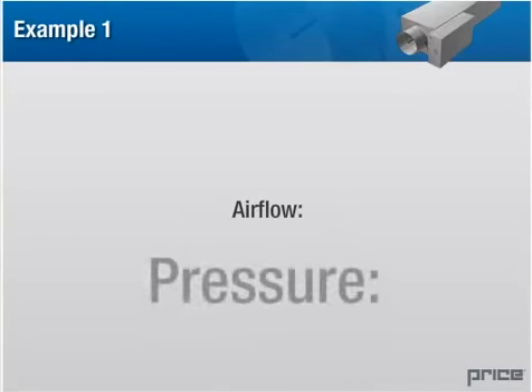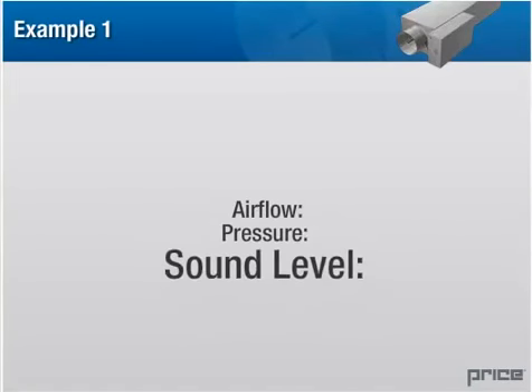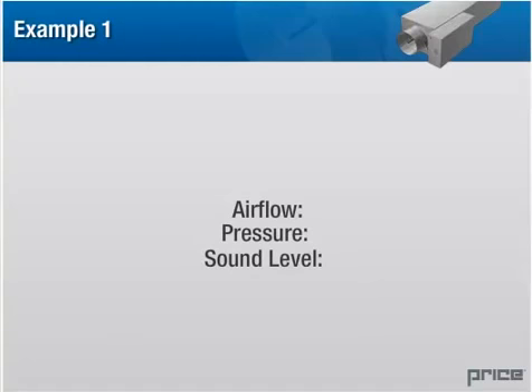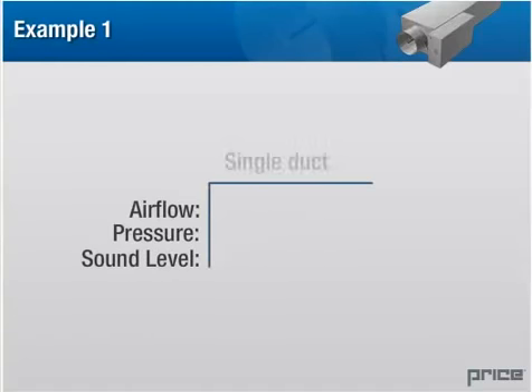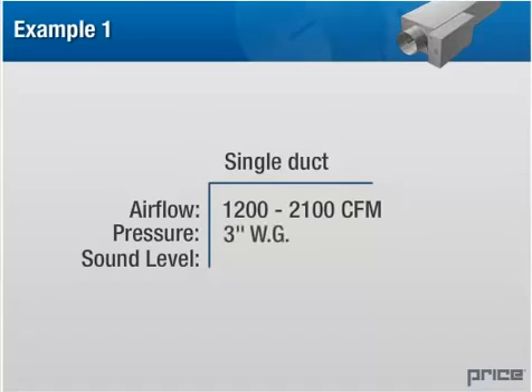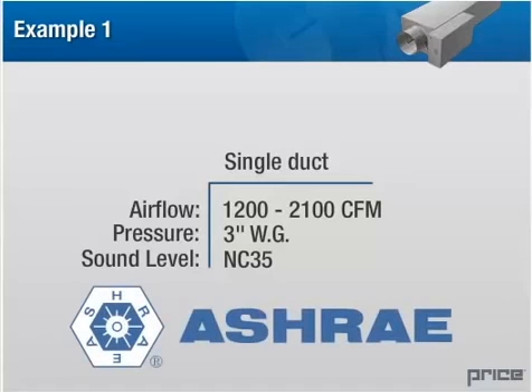Example 1. Once you've determined the airflow, pressure, and sound requirements for a terminal unit, a selection can be made. For this example, we'll use a single duct terminal unit and a requirement of 1200 to 2100 CFM at 3-inch water gauge and an NC requirement of 35 for standard office spaces provided by ASHRAE.